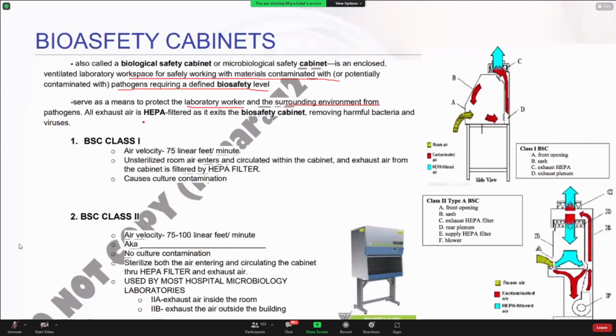All exhaust air is HEPA filtered as it exits the biosafety cabinet, removing harmful bacteria and viruses. You'll learn the mechanism later on. Our HEPA filter is a type of pleated mechanical air filter. HEPA is an acronym for High Efficiency Particulate Air filter.